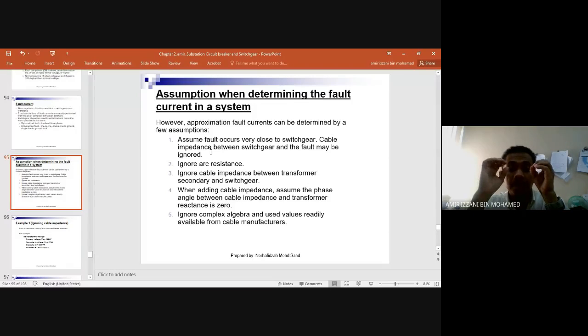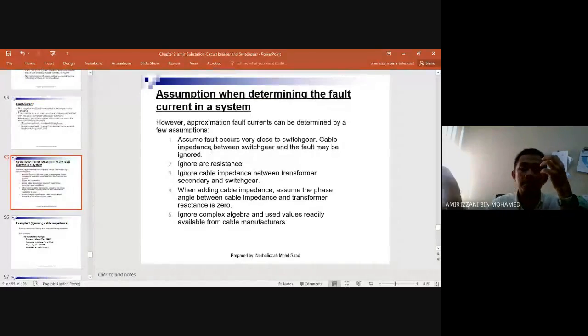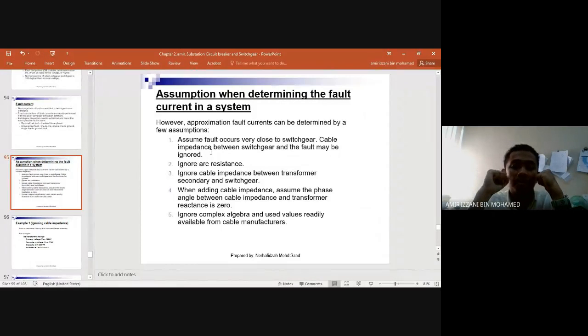Then in the calculation, ignore cable impedance between transformer secondary and the switchgear, because between those we also have cables, so we ignore the impedance. When adding cable impedance, assume the phase angle between cable impedance and transformer reactance is 0. Then ignore complex algebra and use values readily available from the cable manufacturer.